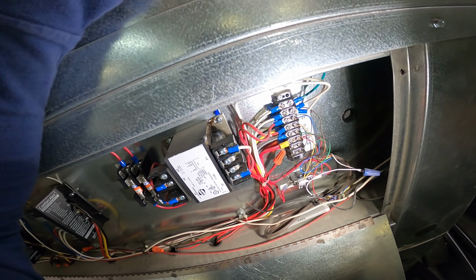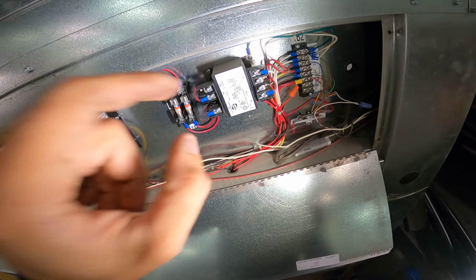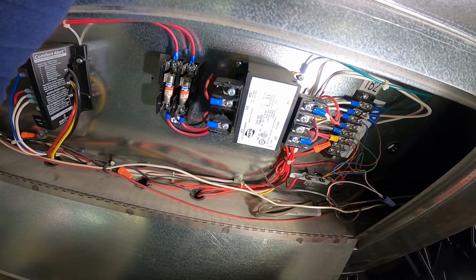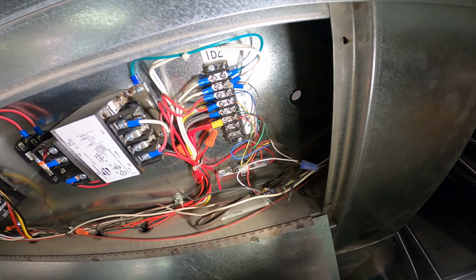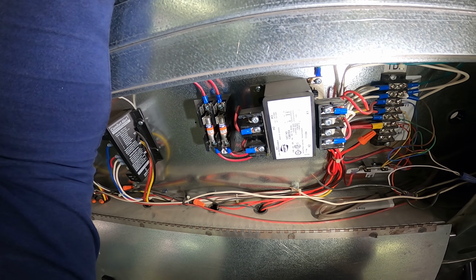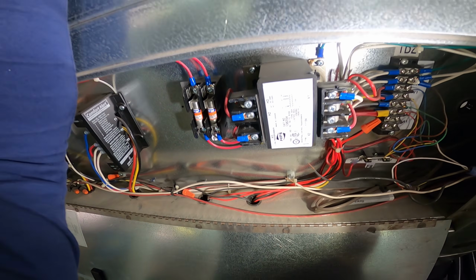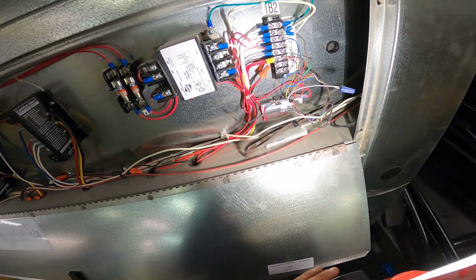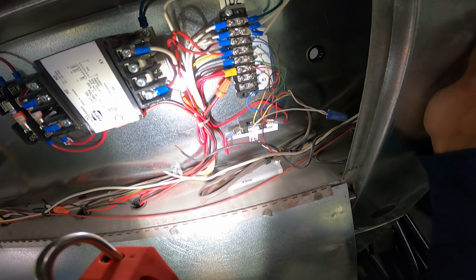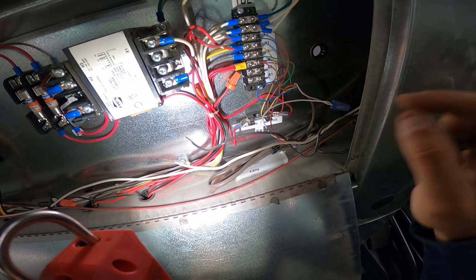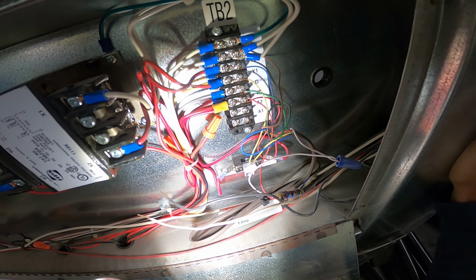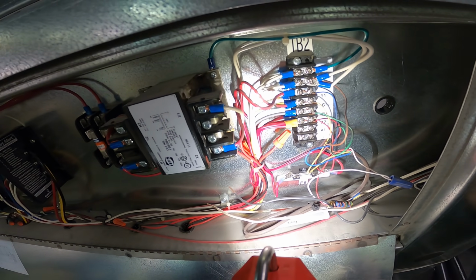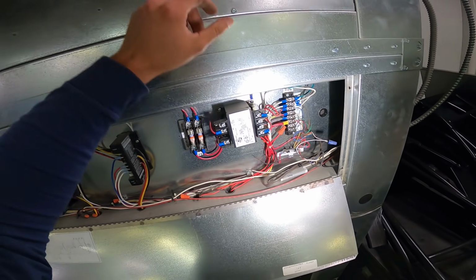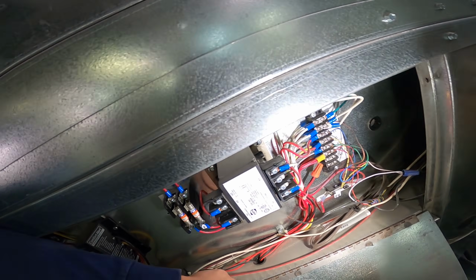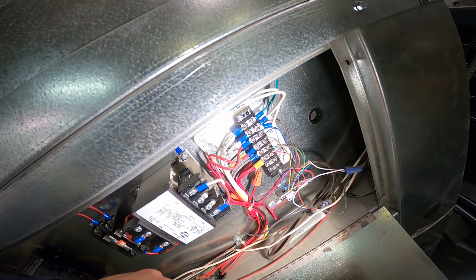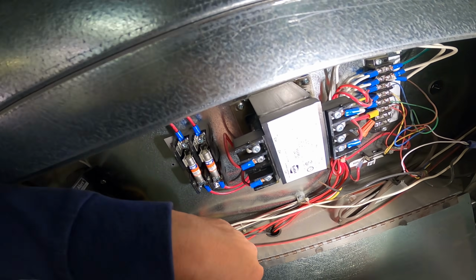And that's going to be speaking with our control circuit here. As you can see, we have a transformer, and let's see, our secondary is 24 volts. So our control circuit is 24 volts, and our line voltage circuit is 208 volts, 3-phase. Next, if we follow here, for R, it comes in and out of a fuse. So that's still our low voltage circuit. That's little protection for our 24 volt circuit, okay? Our 24 volt circuit actually gets fed from this transformer. So we have 208 coming in, and we have 24 volts coming out, feeding our control circuit.